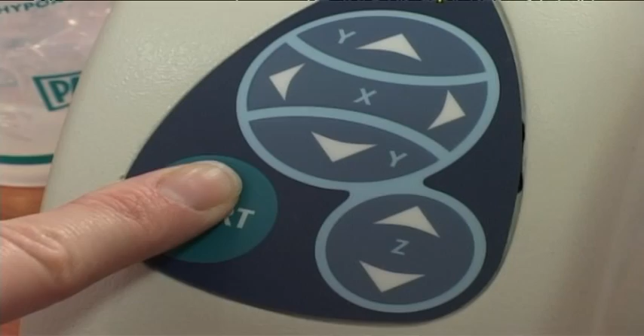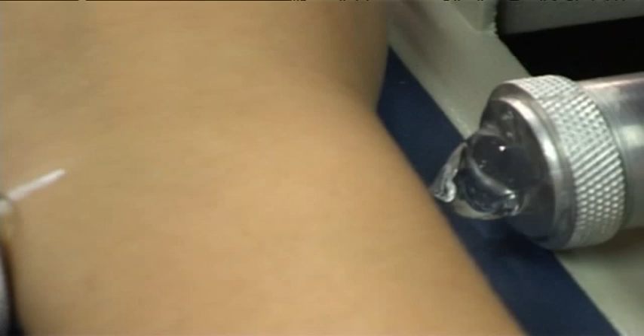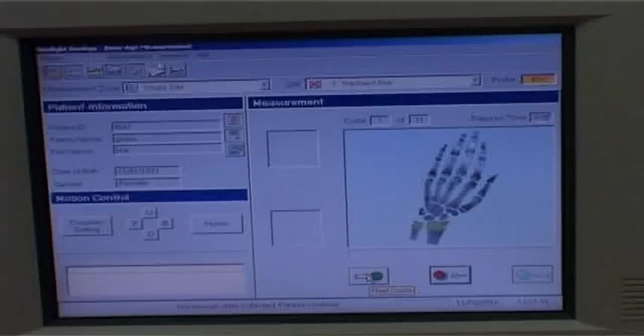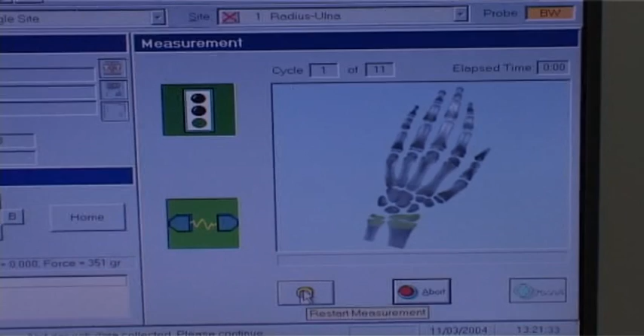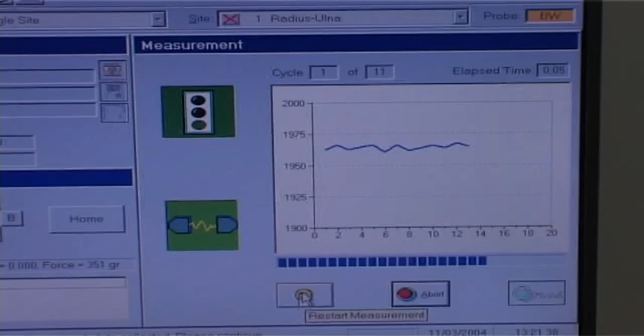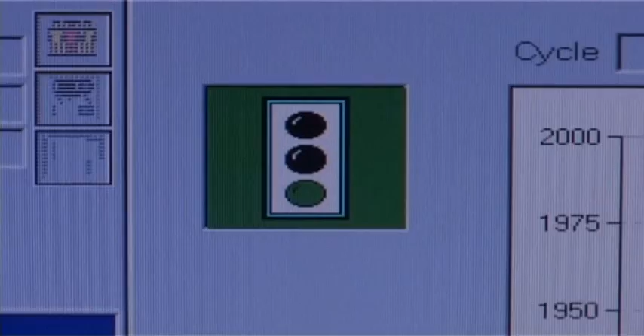The operator clicks the Start button on the screen or presses the Start button on the measurement unit's keypad. This will cause the probes to close on both sides of the patient's arm until pressure equals approximately 500 grams. The first ultrasound measurement of the wrist commences at this point. During measurement, the measurement process is displayed in the form of a building graph. The graph, cycle build, and cycle number, along with the green lights that show ultrasound contact, all indicate to the user that the measurement is ongoing.